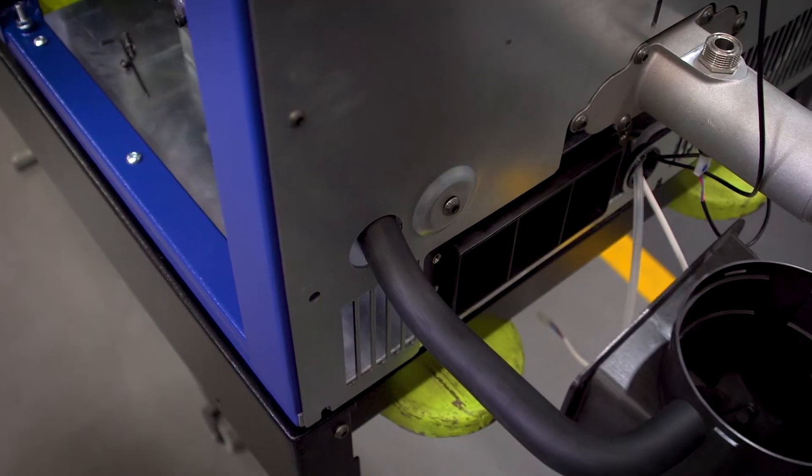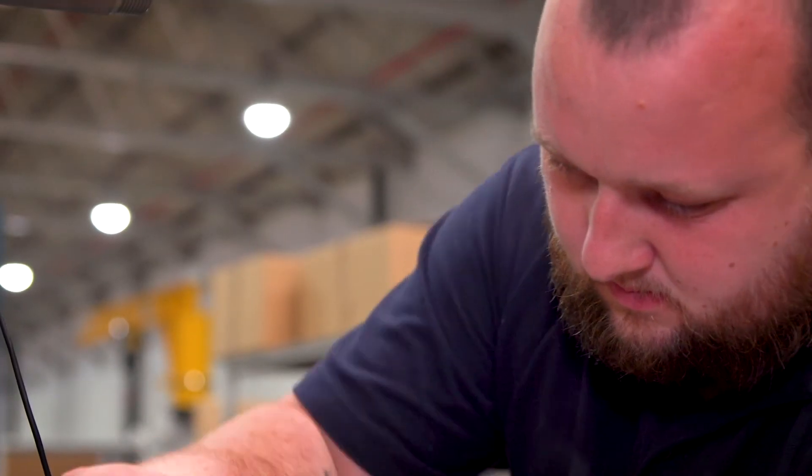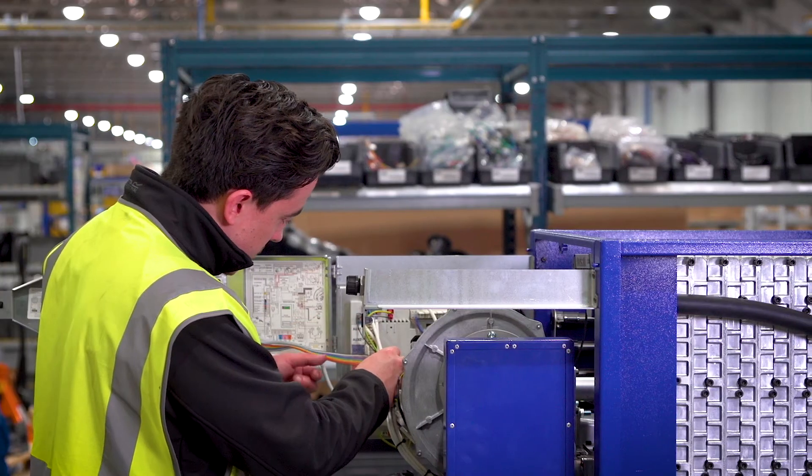We tested it over 30 bar. We did cycle testing — raising the temperature up to maximum and then varying the pressure from zero to six bar — and we did that for half a million cycles.